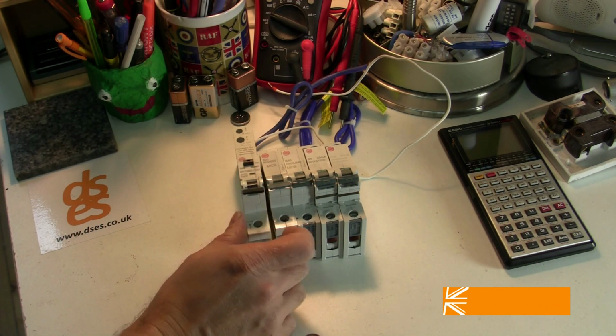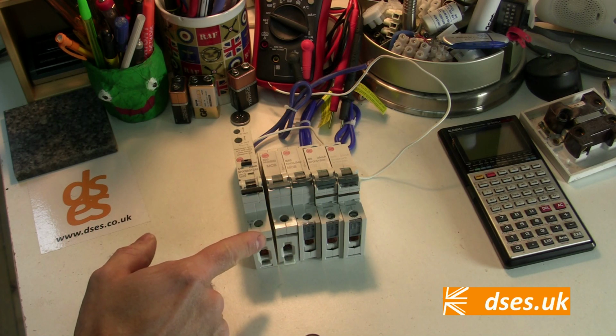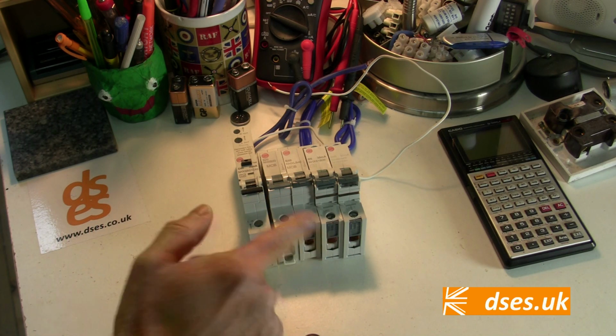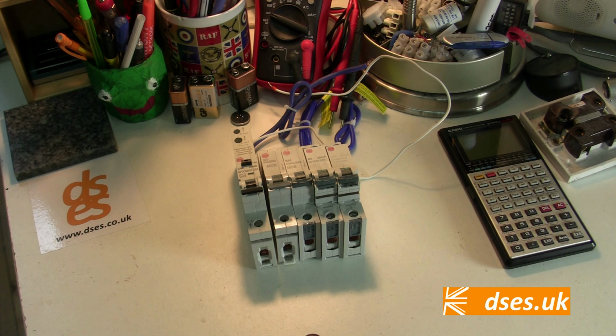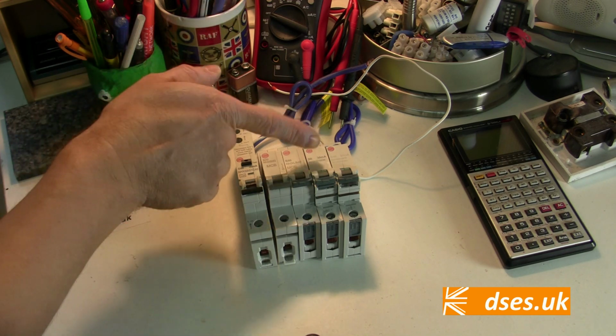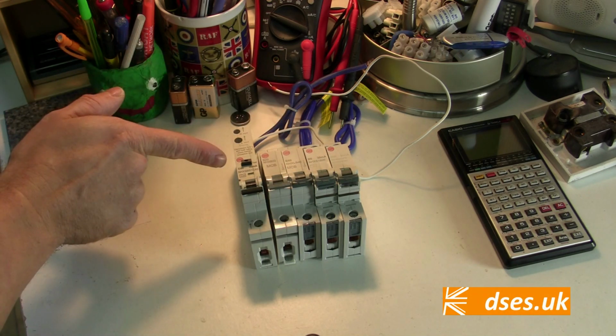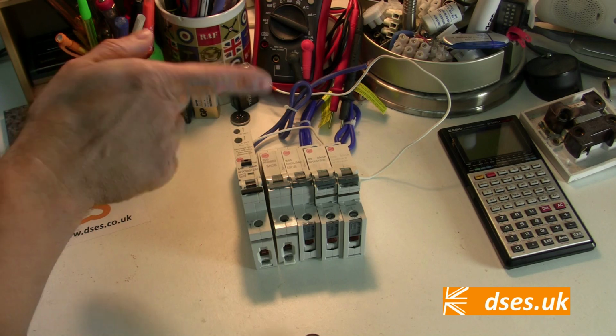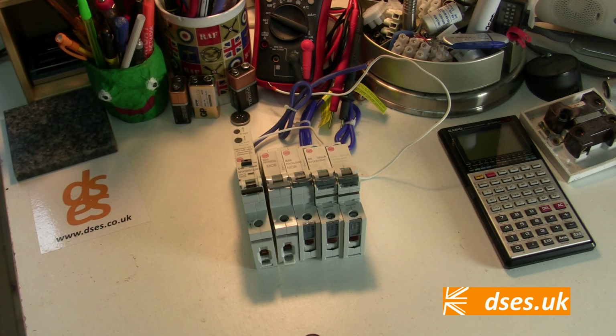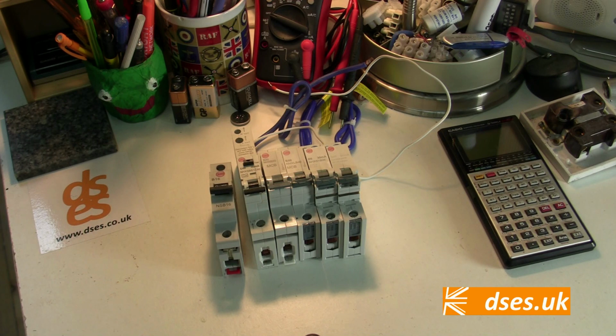which, like NHX, supports the balcony busbar, unlike NHXL or NHXS. So you may get caught out on site, as I've been in the past, by finding yourself rolling up with a newer NHXS RCBO to replace an older NHXS BS1 RCBO, or an NHXL MCB to replace an NHX MCB, or whatever to replace one of the obsolete NSB MCBs, just to throw that into the mix. Christ, what an omni-shambles. Again, this is a nightmare for retrofit, just trying to find the right product that's compatible with what's on site, only to discover the model you bought isn't going to slide into that old consumer unit after all. Why does it need to be this complicated?